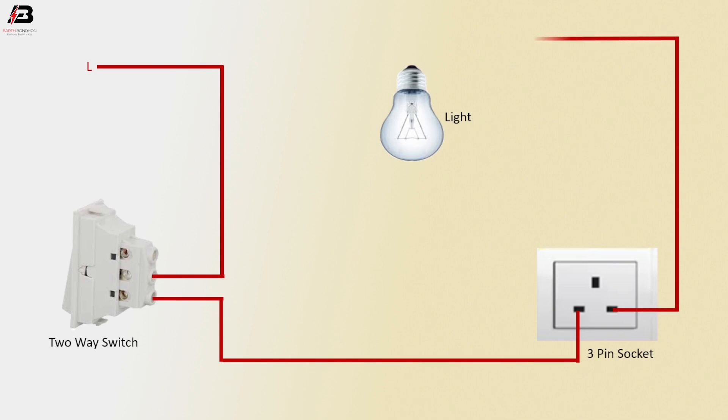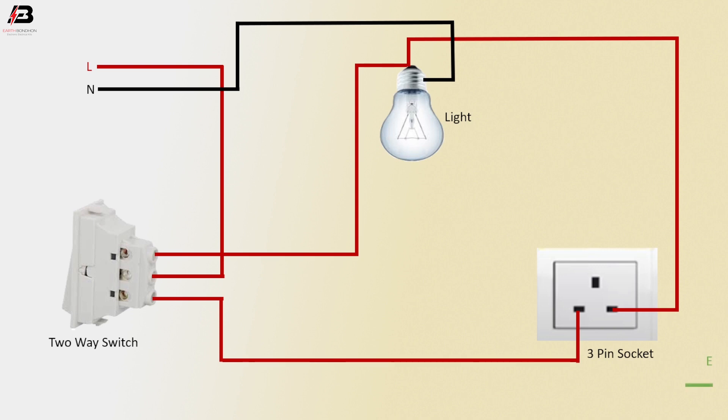Phase connection input to the two-way switch common terminal. Phase connection output from two-way switch L2 terminal to connect the 3-pin socket. Phase connection output from 3-pin socket to connect the light. Another connection output from two-way switch L1 terminal to connect the light. Neutral connection connected to light neutral point. Earth connection connected to 3-pin socket earth point.